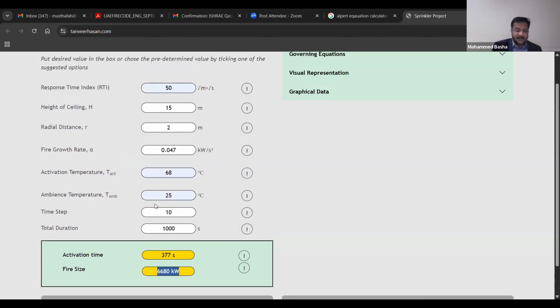But can we take this blindly? I would say no. Why? Because based on one sprinkler activation, defining the Q value is really not a conservative approach, because such a 6 megawatt fire cannot be controlled by one sprinkler. One sprinkler can take a maximum of 800 kilowatt to 1 megawatt of fire at a ceiling distance of 3 meters, at a 3 bar pressure basically.